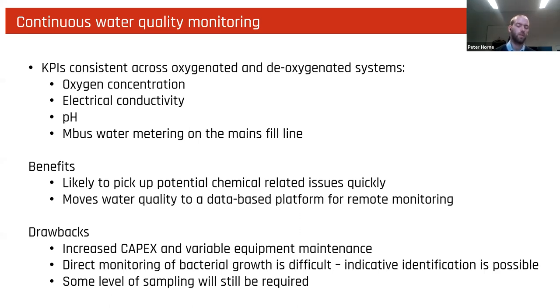So we can pick up chemical related issues almost instantaneously, and it also moves water quality onto a data-based platform, so historical data can be stored away much more easily. It removes the requirement for a paper trail throughout pre-commissioning, which, you know, contractors are busy enough as it is. It may be a benefit from that perspective. The reason I say chemical related issues is because we still may not be able to get bacterial analysis sorted, due to the complexity of the biological metabolic pathways that nitrate reducing bacteria and sulfate reducing bacteria tend to adopt.